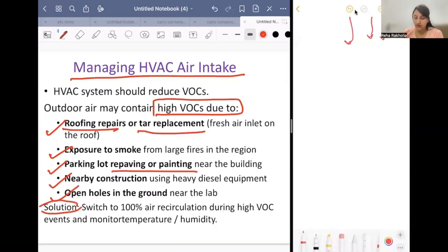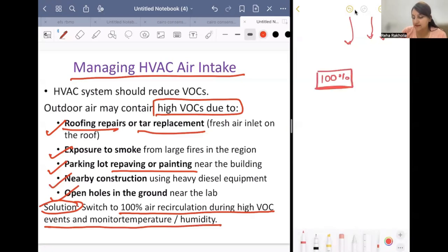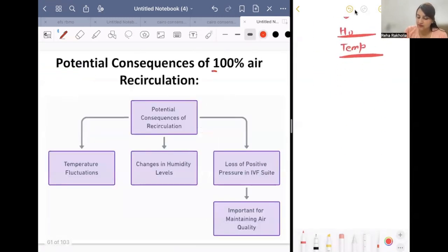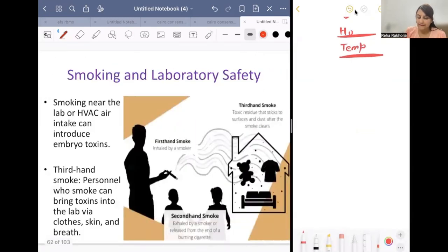So what is the solution? The solution is to switch to 100% air recirculation during a high VOC event and monitor temperature and humidity. We'll use 100% recirculating air instead of outside air. But the disadvantage is that humidity and temperature won't be maintained if we use 100% recirculating air. Potential consequences of 100% air recirculation are temperature fluctuation, changes in humidity level, and even loss of positive pressure in the IVF suite.